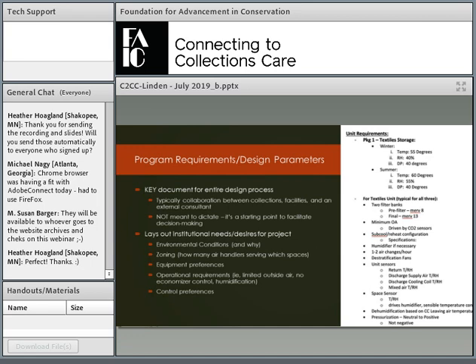Operational requirements: I have a storage environment, we're in the middle of a metro geographic area, I don't want to use a lot of outside air—I'd prefer to use no outside air. Please design the system to make that possible. I don't want an economizer, I don't want to use free cooling because I'm worried about pollution or moisture control. I need to humidify in my setting, even though it might not be typical for what the engineer has worked with in the past—I need you to install a humidifier so we can maintain the minimum relative humidity.